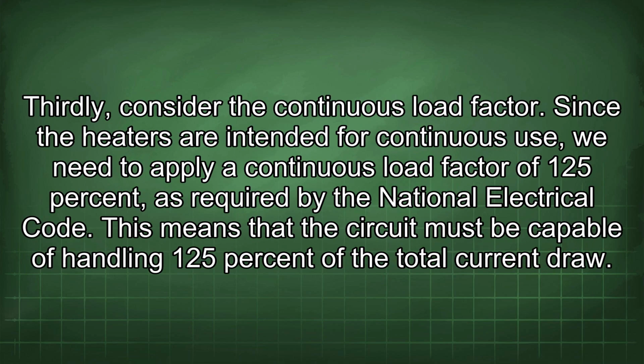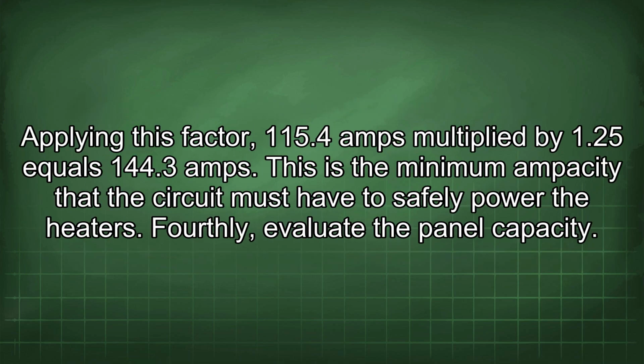Thirdly, consider the continuous load factor. Since the heaters are intended for continuous use, we need to apply a continuous load factor of 125% as required by the National Electrical Code. This means that the circuit must be capable of handling 125% of the total current draw. Applying this factor, 115.4 amps multiplied by 1.25 equals 144.3 amps. This is the minimum ampacity that the circuit must have to safely power the heaters.